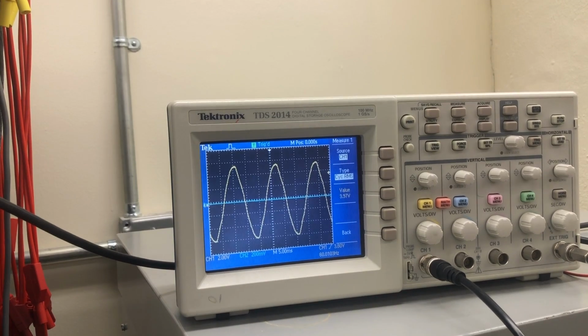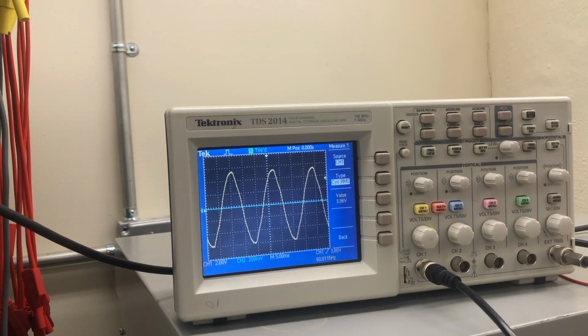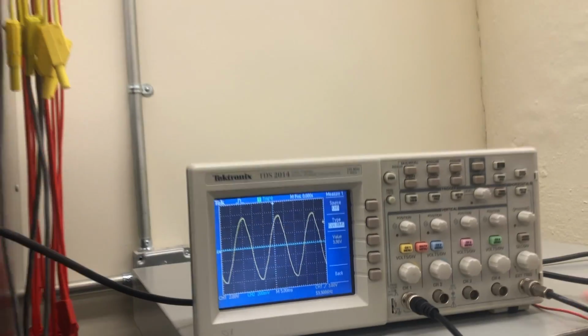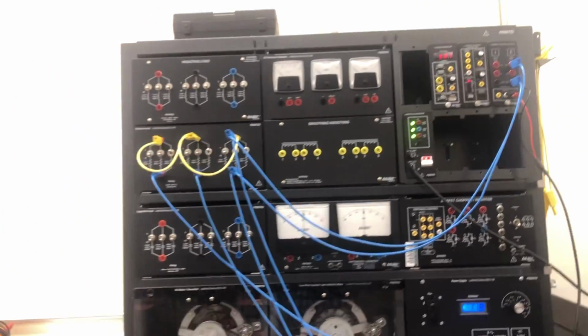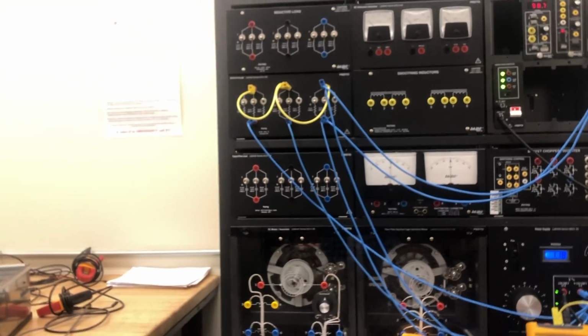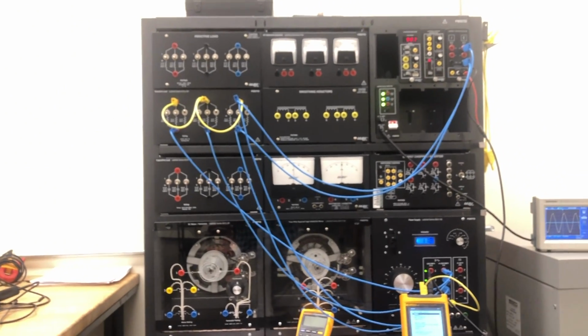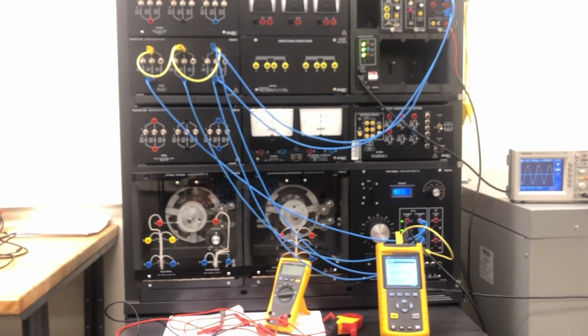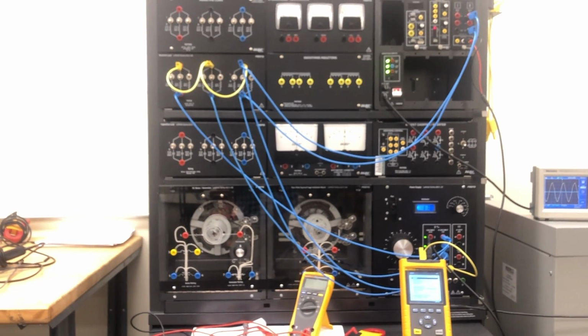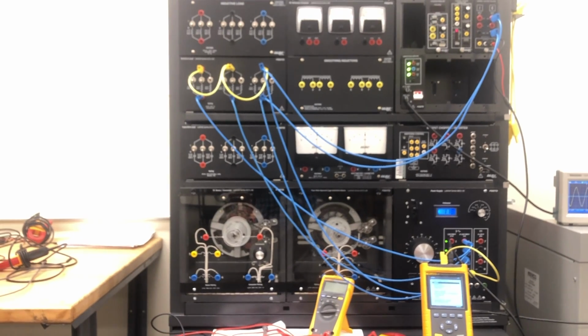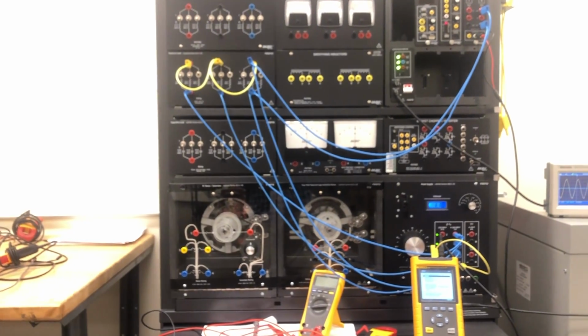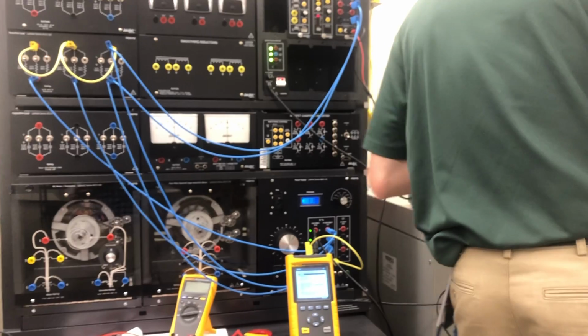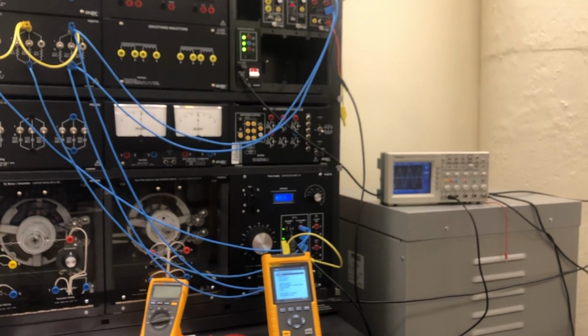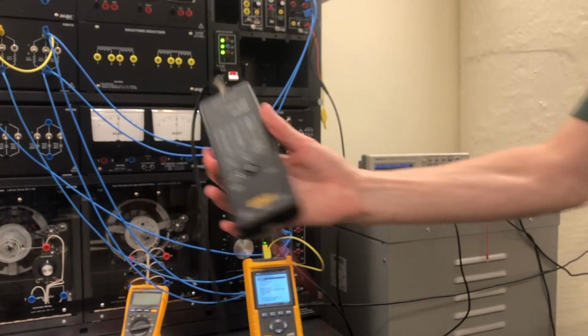The other way to get a voltage waveform on here is to use one of these high voltage isolators. These are very common in the field. I have one of these at work. They can isolate very, very high voltages compared to these. This is good up to 1,000 volts. They look a little something like this. These can plug directly into wherever you want to measure.